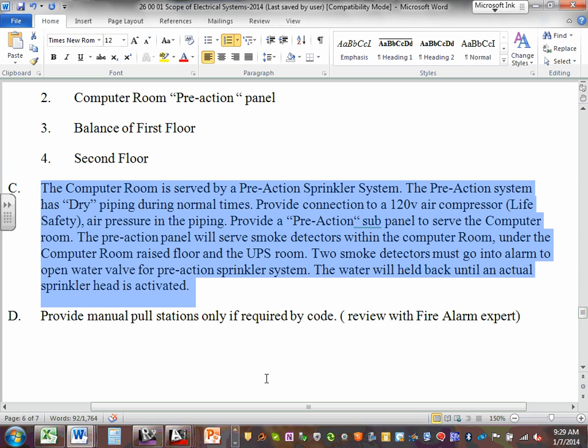You can also do something called pre-action, which is like a dry pipe system - it fills your pipes with air and usually works in two stages. A smoke detector must go off, and a head must have melted, before water is released. Your head usually melts first, releasing the air and dropping pressure in the pipe. Then if a smoke detector goes off confirming there's definitely a fire, a valve opens and dumps water everywhere. So it's two-stage, giving a bit more certainty.